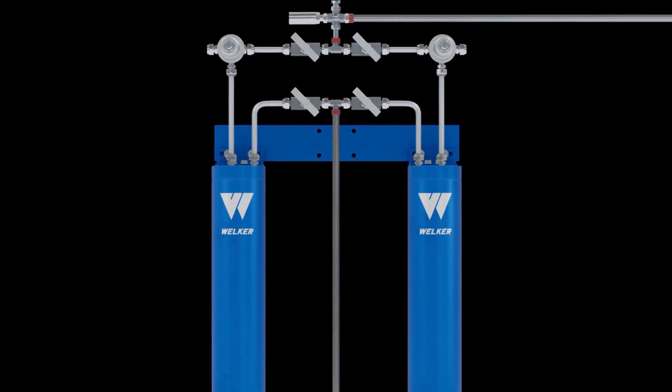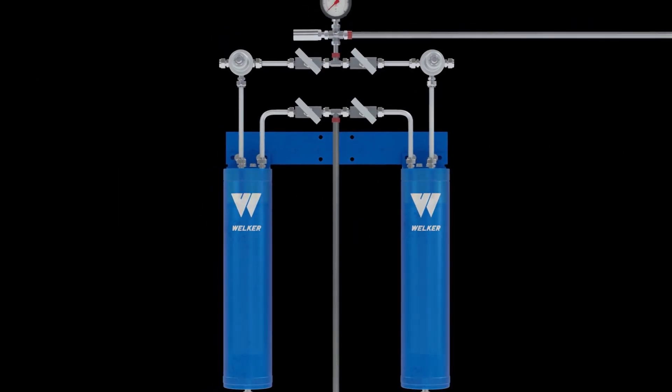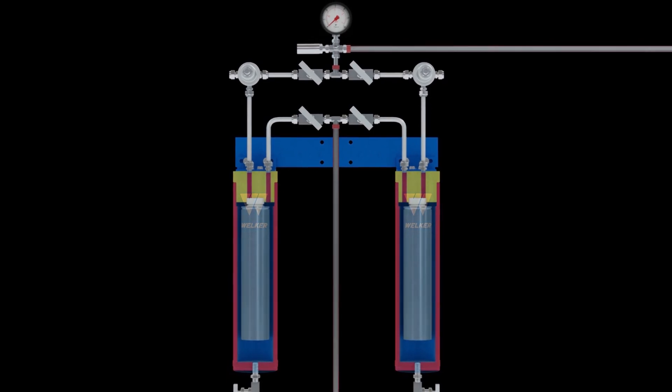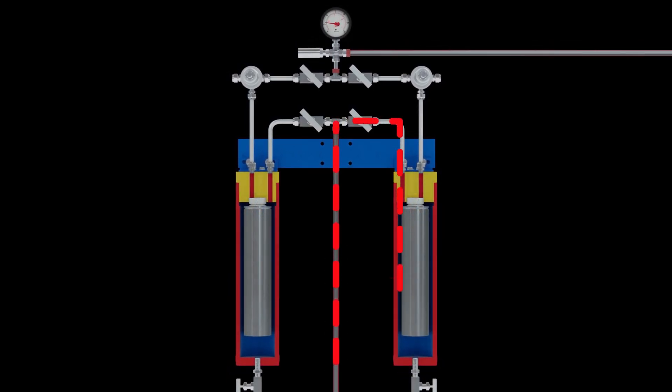Our Clean Flow Plus systems offer the superior protection of the Clean Flow but with the added benefit of automatic backup filtration. In these systems, the incoming natural gas is conditioned by the primary filter dryer and regulator. When the primary filter cartridge needs to be replaced, incoming flow is automatically diverted to the backup filter. This integrated backup system enables the Clean Flow Plus to operate for longer periods of time between cartridge changes.